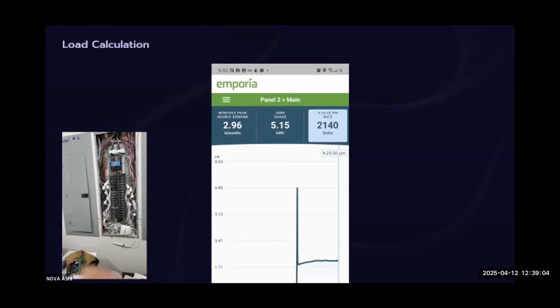Out of these three panels, we consolidated and put the essential loads into panel two, and moved the other circuits that weren't essential to the other panels. Over a week's time I put this smart metering system in here, as you see these CTs, and we monitored his electricity for over a week. Then we saw what his peak load was to make sure the generator would be able to sustain and carry what he wanted as far as his loads. So that's one way that we do that as well.